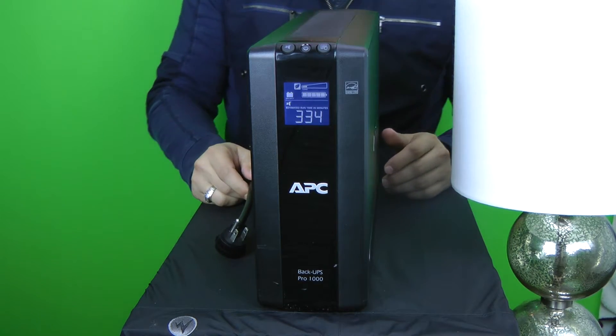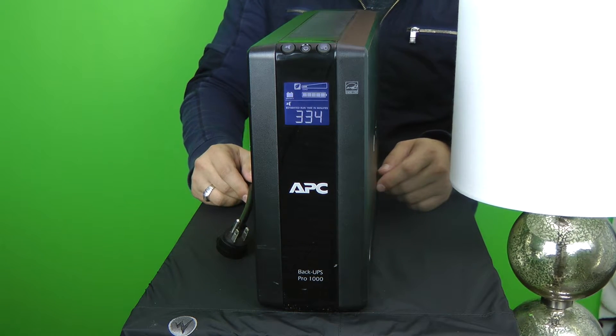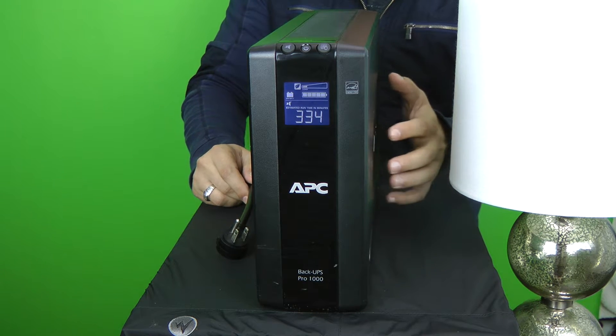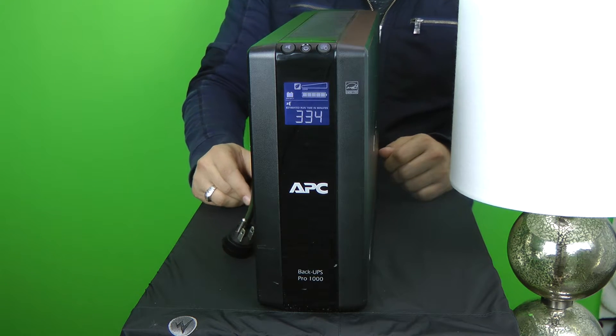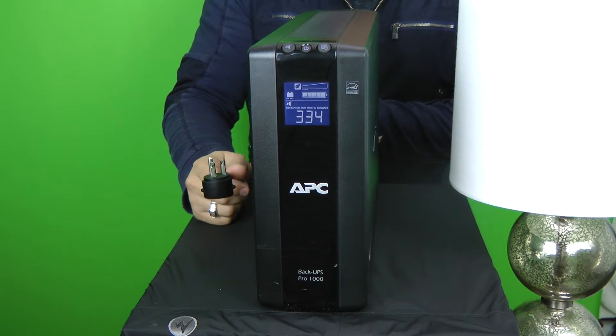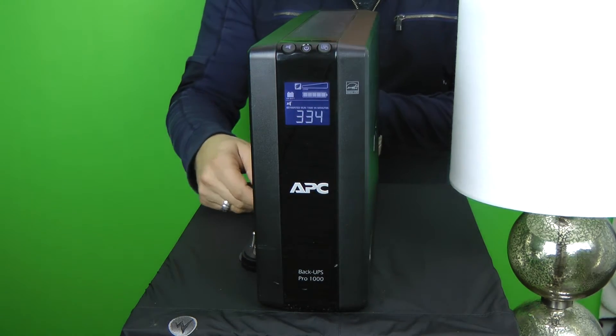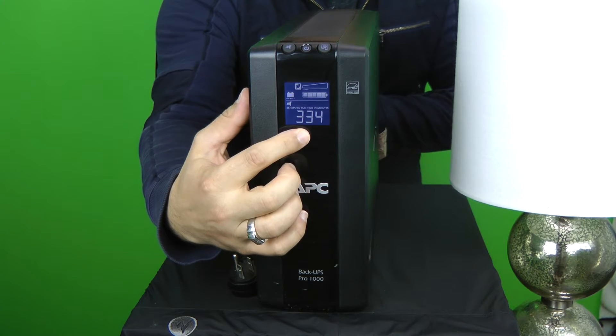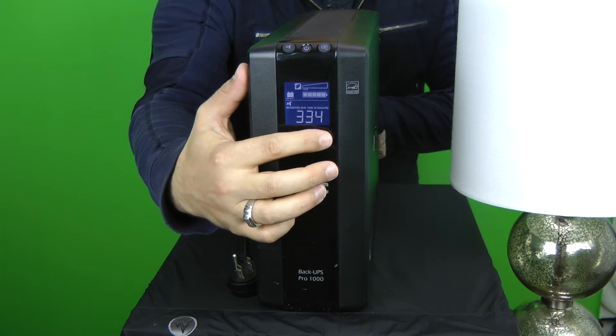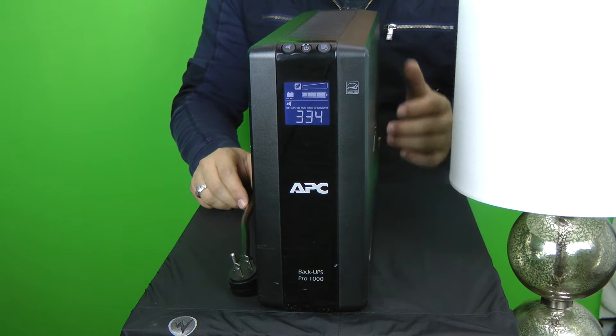This is an LED lamp so don't worry too much about that number, but what you are seeing is that the lamp stayed on — and that's the crazy part. This was pulled from a production unit. So if the power would have gone out, or if there would have been a brownout — a flicker of electricity — even if it's for two seconds, the entire system could have shut down because of an improperly configured device. In this case, they didn't read the instructions on the battery that literally said flip it over, green side goes up, slide it in, and that's it.